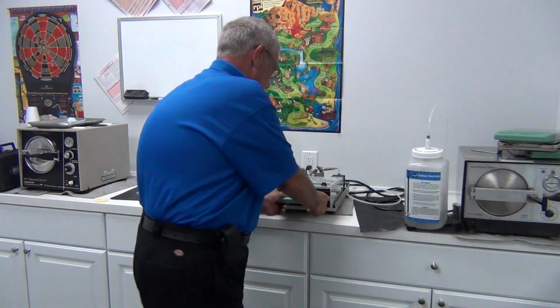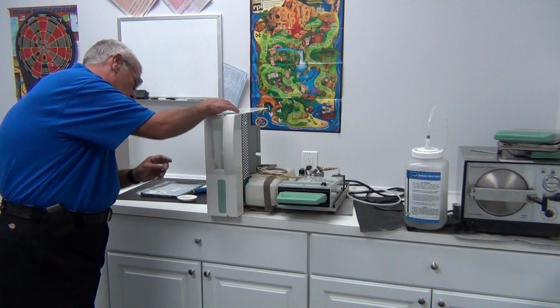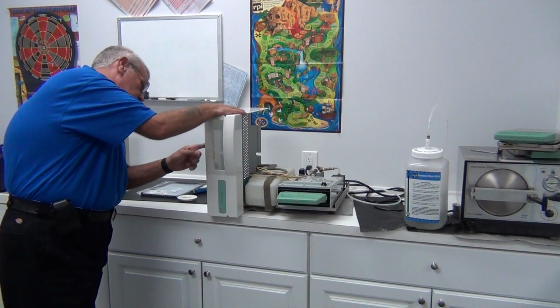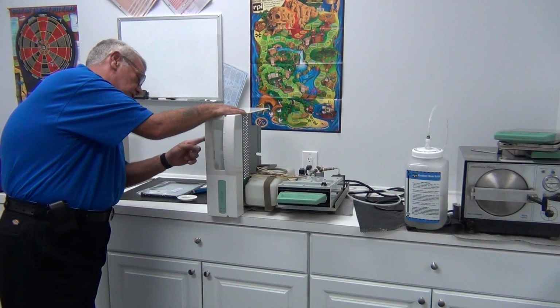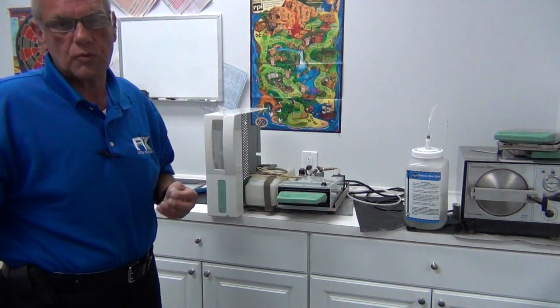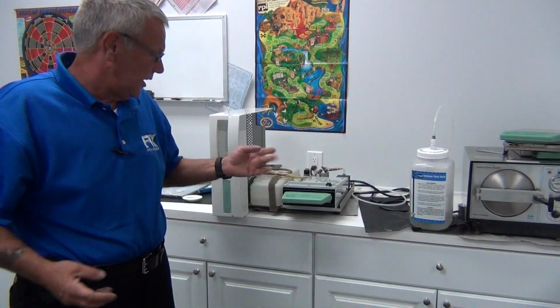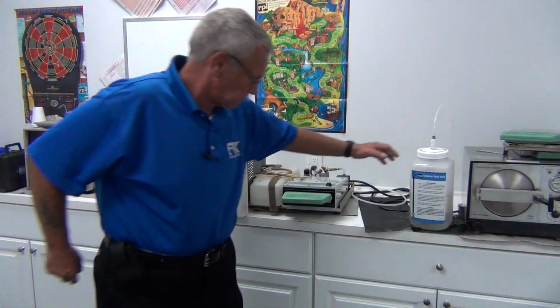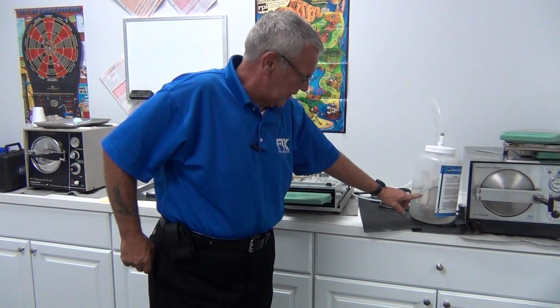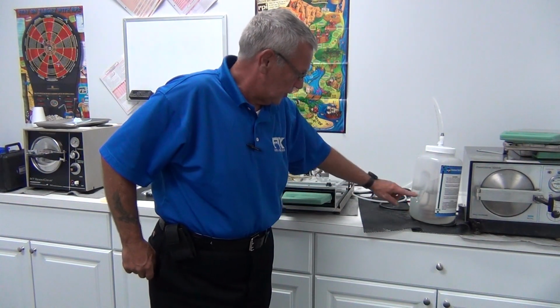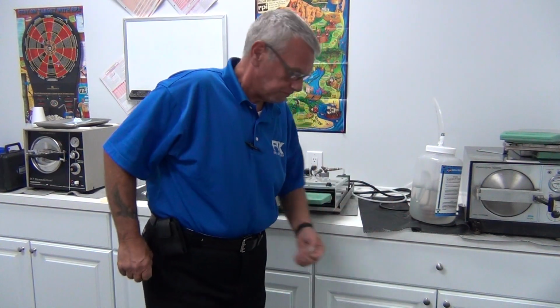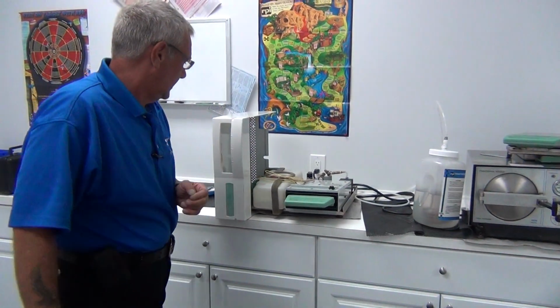Okay, it's okay to remove our cassette now, but we're not going to. We're going to check the dry on it. We'll hit the dryer mode and start. And you hear our compressor starting, our dryer compressor, which is what we changed the filter on, and we're looking for the check valve. You can actually hear air exhausting through the tubing into the collector bottle. Wet air. It's forcing wet air over the cassette. So we know the dryers are working good, the filters are all intact.